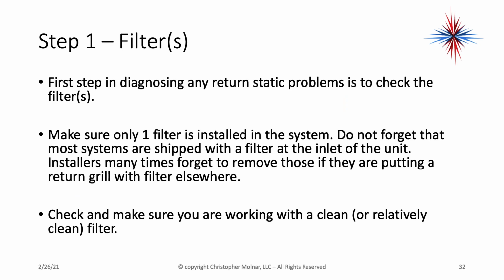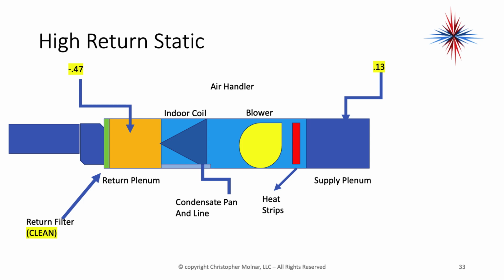First step is to check the filters. Make sure there's only one filter installed in the system. Do not forget that a lot of systems are shipped with a filter in the inlet of the unit to protect the coil. Installers many times forget to remove these if they're putting in a return grill with a filter someplace else. Check and make sure you're working with a clean or relatively clean filter. Don't do diagnostics with dirty air filters. Okay, you got to have a clean filter.